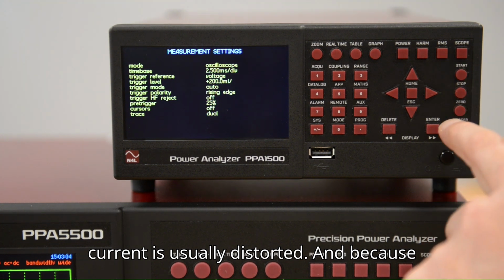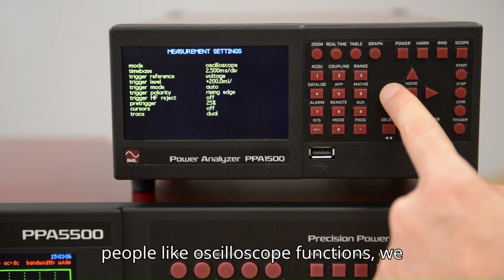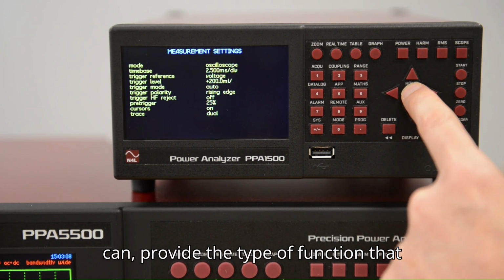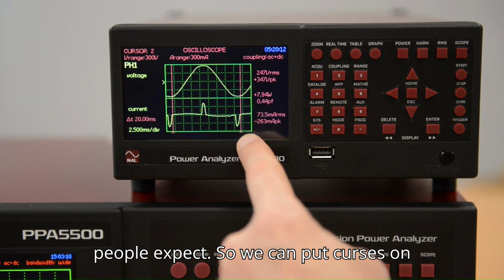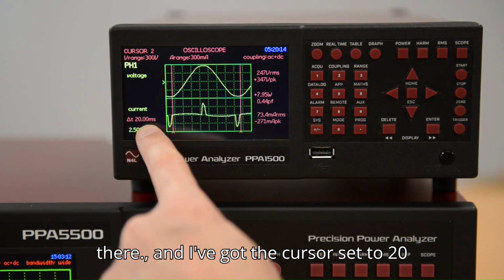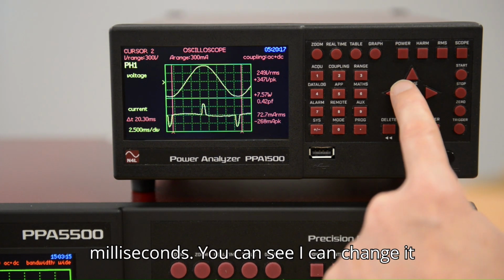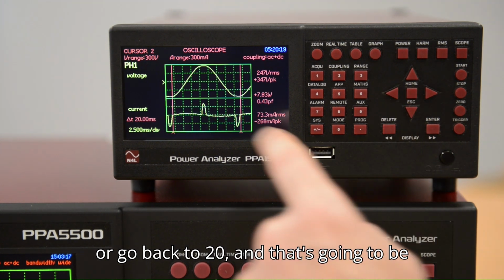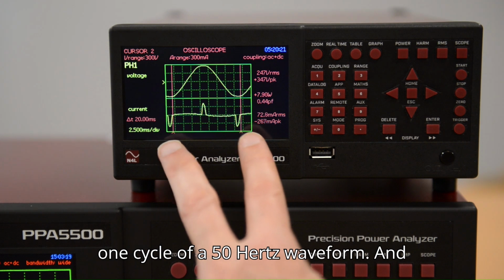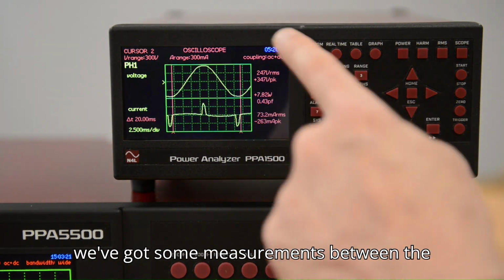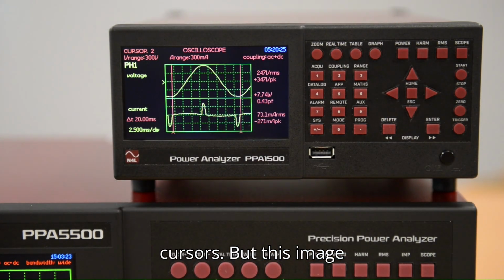And because people like oscilloscope functions, we can provide the type of function that people expect. So we can put cursors on there, and I've got the cursor set to 20 milliseconds. You can see I can change it or go back to 20. And that's going to be one cycle of a 50 Hertz waveform, and we've got some measurements between the cursors.